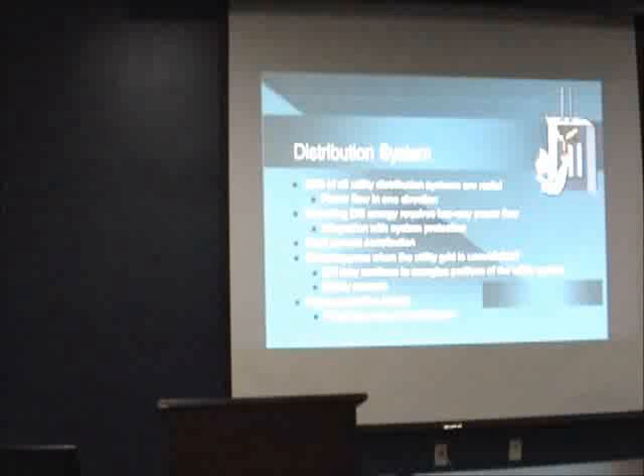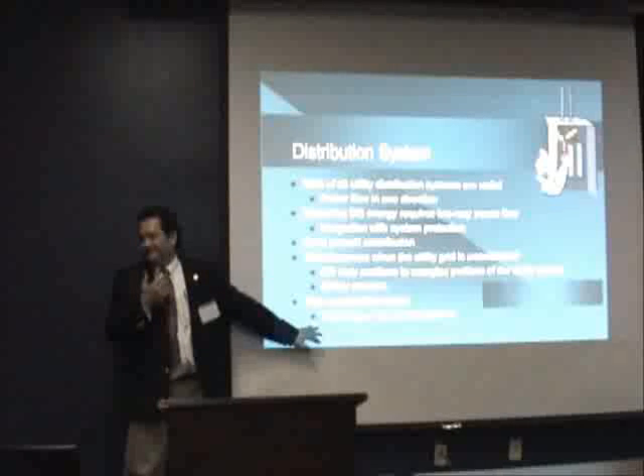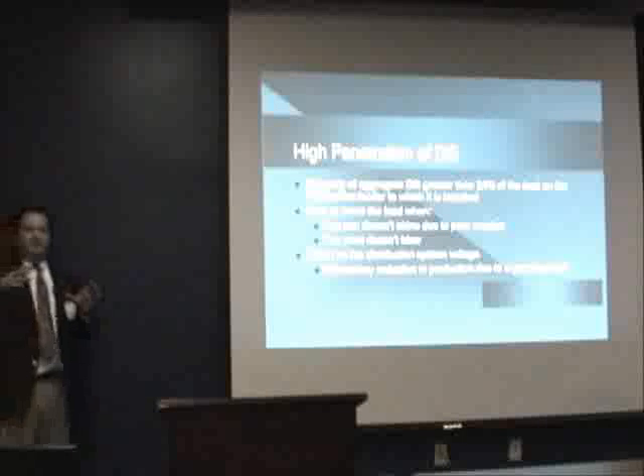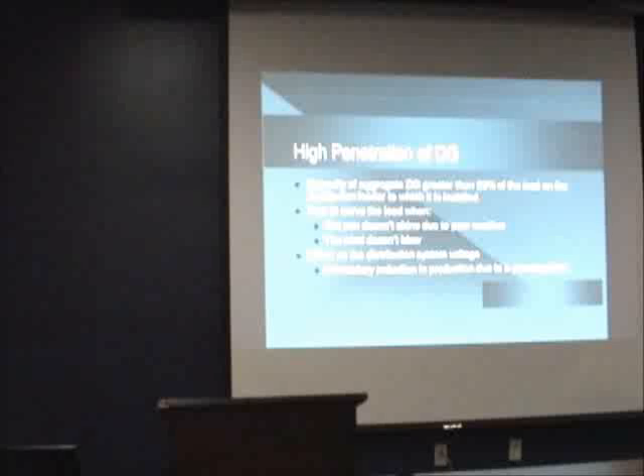And then high penetration. Talking about a lot of guys. Now, on my company, again, there's about 650,000 meters, I think, and we got almost 40 customers with solar panels and wind turbines. Now, that is nothing, right? But think about one distribution line in Tampa, Florida, in one neighborhood. Every house has got a solar panel on it, right? High penetration. Think big, lots of installations. That can be problematic. So studies have been done and said, look, the amount of electricity that's being consumed on this line, the maximum amount of distributed generation you can put on is 20% of that level, right? We got to get past that barrier, all right? How do we get past that barrier?